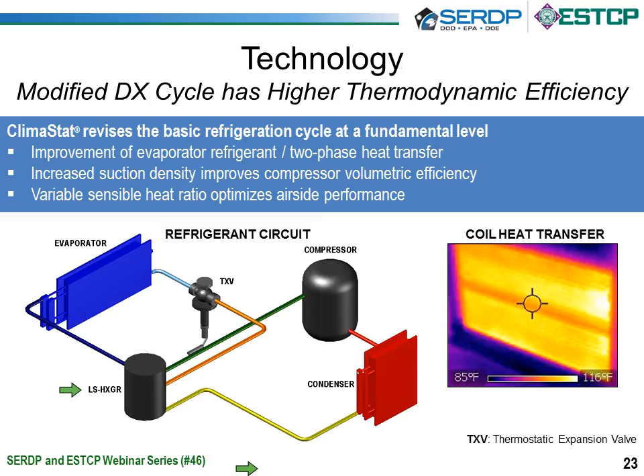And that means there's more liquid going into the evaporator, and it improves the refrigerant two-phase heat transfer in the evaporator coil. The second thing it does is separate out the liquid and vapor so that we can have liquid all through the evaporator coil and not have to waste any of the heat transfer surface area superheating the refrigerant. And the end result is that the refrigerant that reaches the compressor is colder and has a higher density, so we get improved compressor volumetric efficiency. And finally, taking advantage of these things, we can make adjustments and control on the air side of the air conditioner to improve performance.